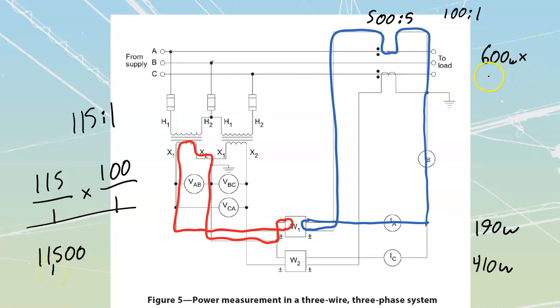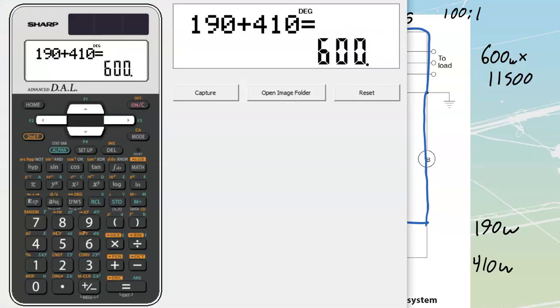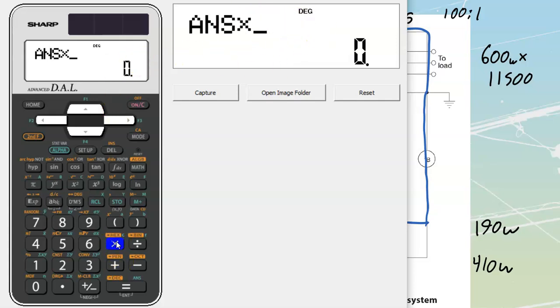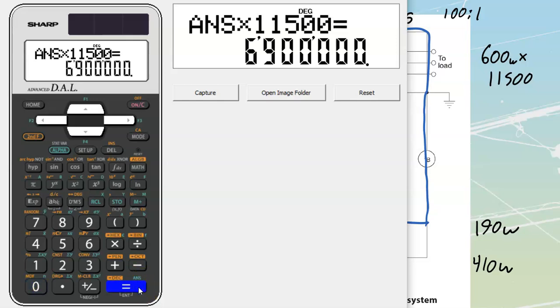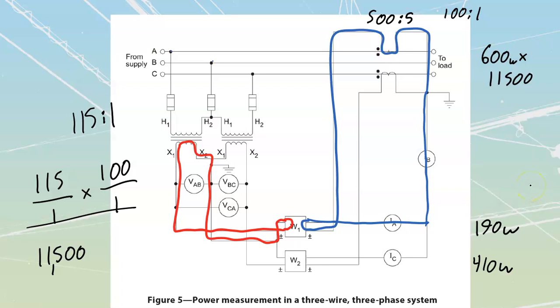So my wattmeter total is 600 watts, which is adding those two up, multiplied by 11,500. 600, which we already have in here, times 11,500, which gets me up to a value of 6.9 megawatts. My total power is going to be 6.9 megawatts. Now I'm going to place that in over here because we're going to start to build a triangle. 6.9 megawatts. Beautiful.